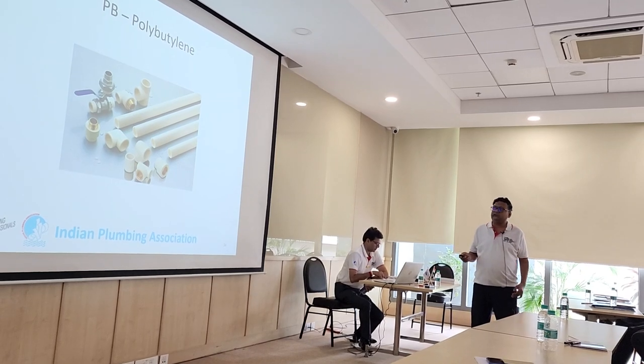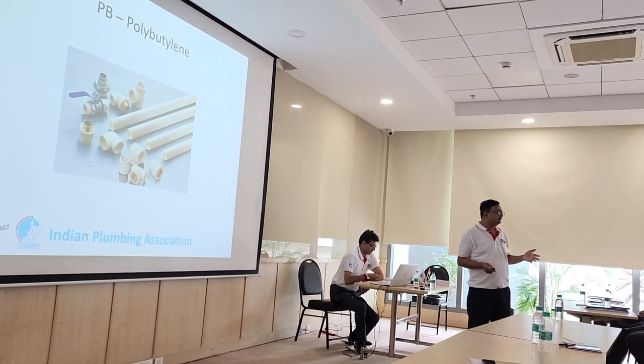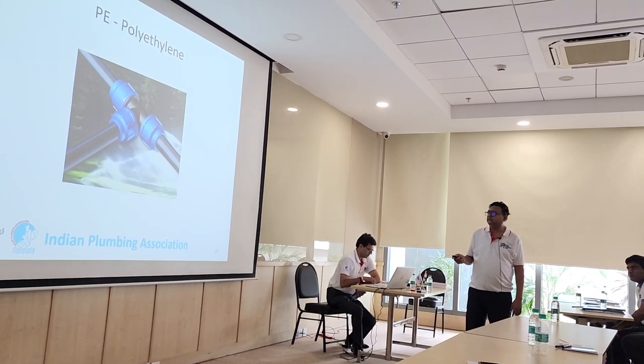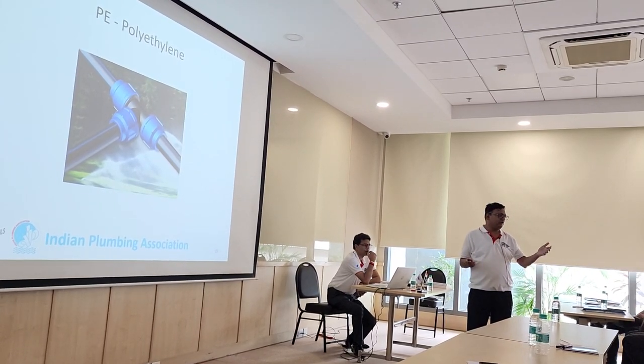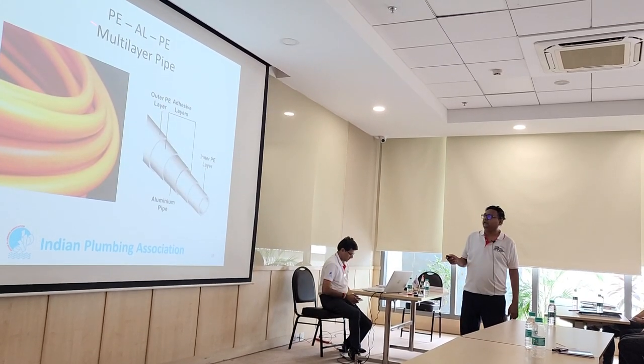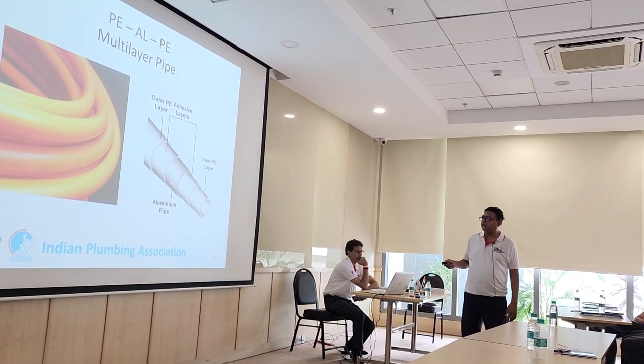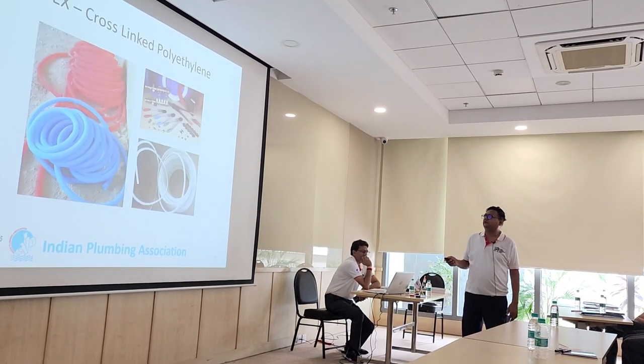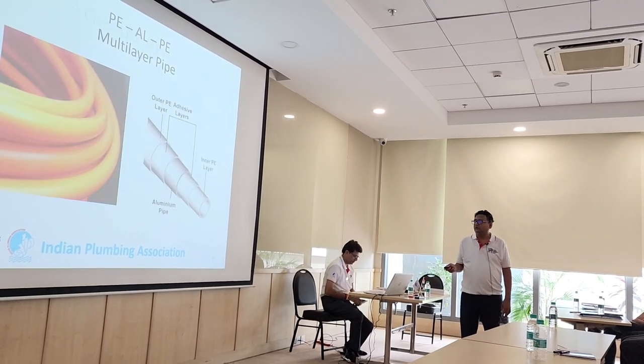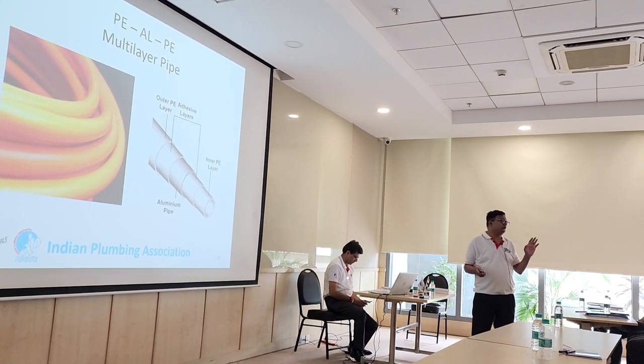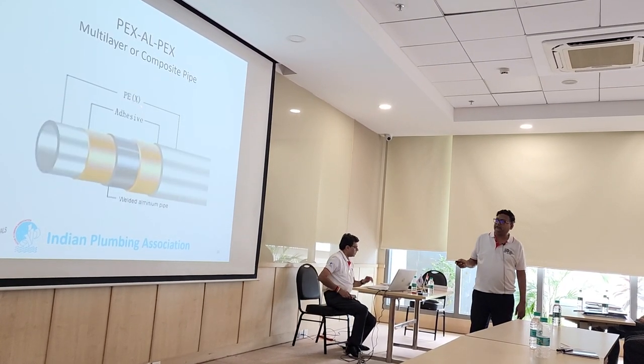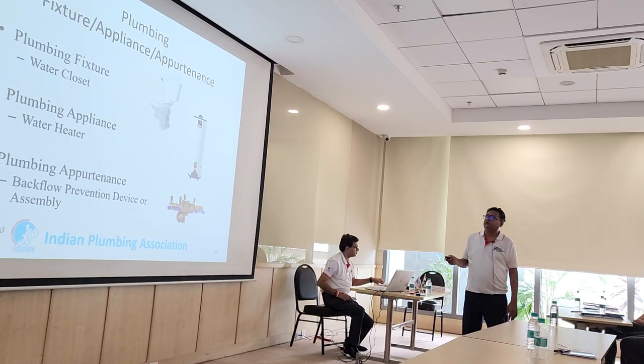Polybutylene — this is a type of pipe; it came about 5-6 years back but is not very popular. Polyethylene is a different type of plastic or PVC family. PE-AL-PE has three layers: one is PE, then aluminum, then again polyethylene. PEX is cross-linked polyethylene — a flexible type of pipe. PE-AL-PE is also flexible but only to a certain extent. PEX is more flexible. PE-AL-PE is also called a multi-layer composite pipe.